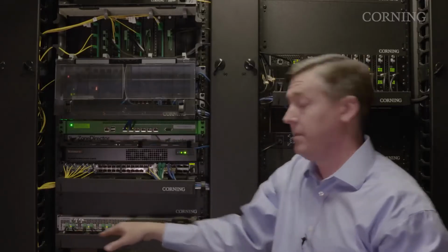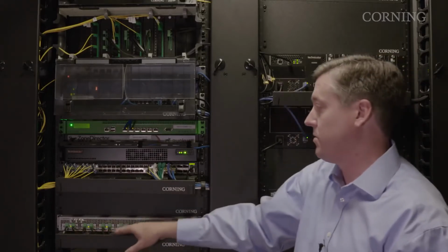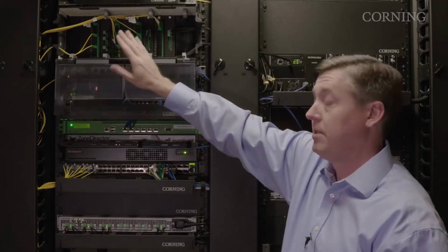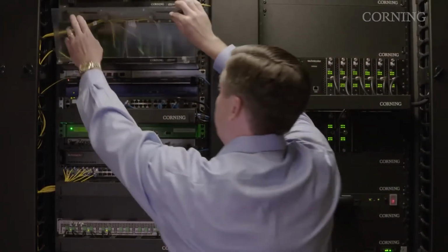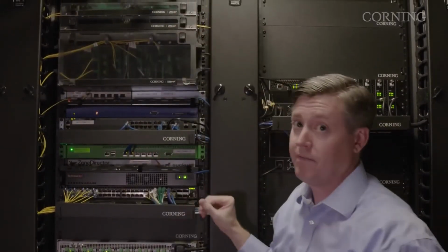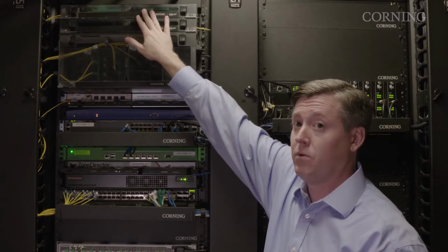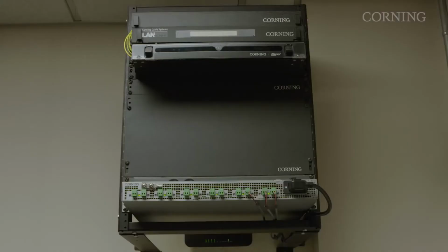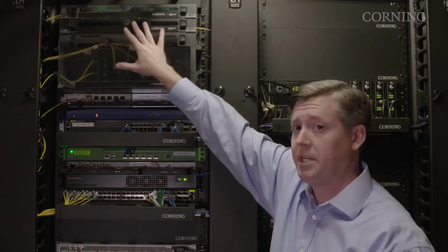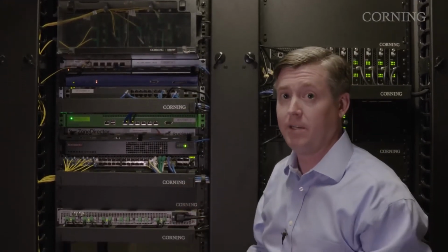That power is coming from the power supply unit, Corning's power supply unit, or the PSU. So these are 100-watt circuits which are patching from the PSU up to the patch panel, leaving out the back via composite cable. I also have 2 patch panels at the very top. These are my connections to the other IDF closets in the facility. So I have a closet on the 4th floor, which is serving floors 2, 3, and 4. Then I also have a small closet in the back of house, which is serving some back of house office, like the general manager's office, printers, the property management system, etc. But again, this is the nerve center. From this point, I've got fiber out, and everything is being fed via a deep fiber network.